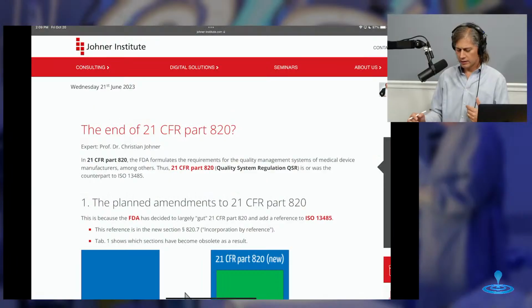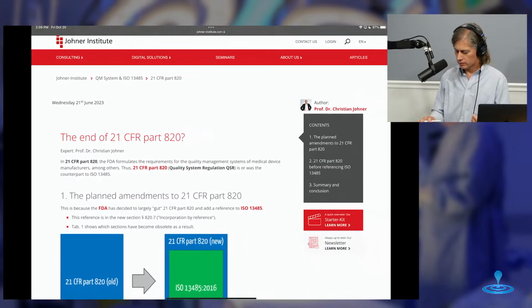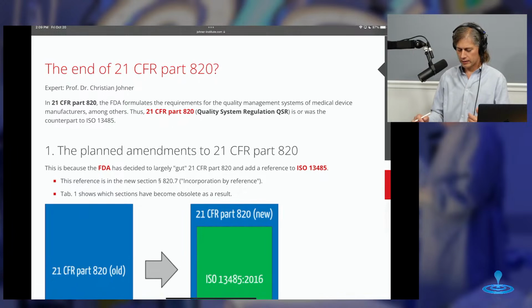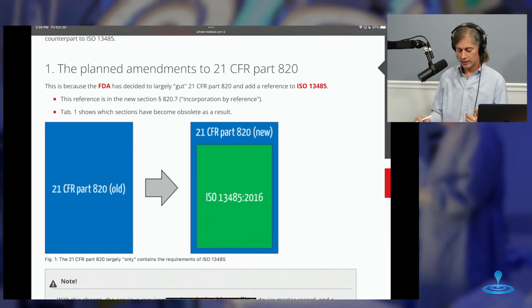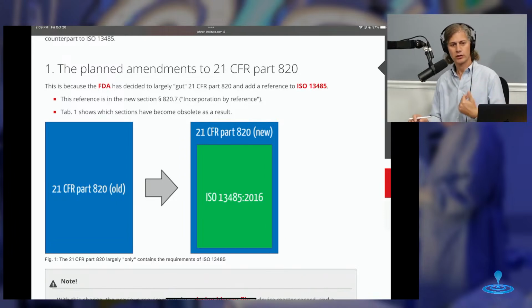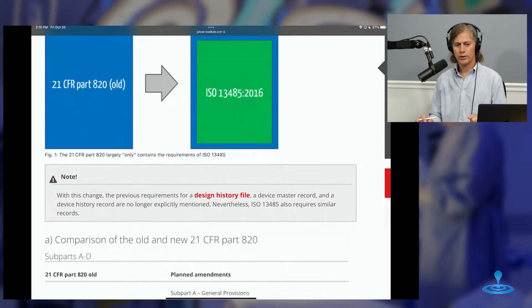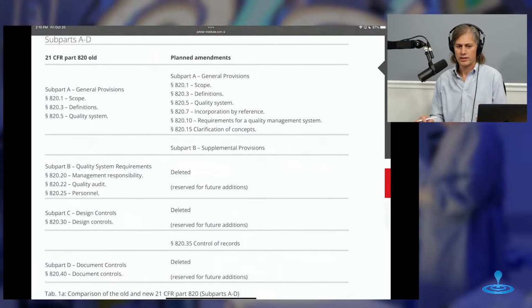And I want to show you something here. This is from the Johner Institute, and credit where credit is due. Dr. Christian Johner has a whole article on this. But I love this very, very simple graphic right here. The planned amendments, this is as of early 2022, it's been nearly 2 years. We'll talk about this later. The FDA has largely decided to gut 820 and add a reference to 13485. Incorporation by reference. In other words, the old 820 looks like what's on the left, and the new 820 rips a bunch out and then places 13485 in. The goal there would be to obsolete certain parts of 820 because they're contained in 13485. So they're not going to rip 820 entirely out. You still have to comply with it, but it is changing.